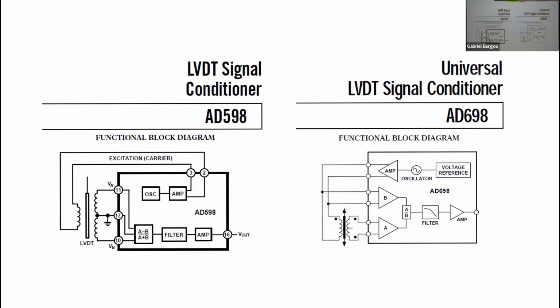Now what happens? The LVDT works as a transformer, transferring flux from the primary to the secondaries. If you reduce the flux, the secondary outputs go down. But it isn't because the core moved that they went down, which is what you're trying to measure—it happened because the temperature went up. So how do you know whether the output change was due to temperature or due to core motion?